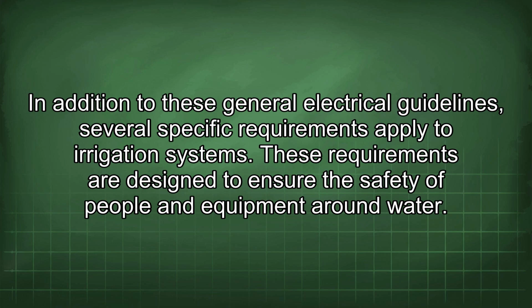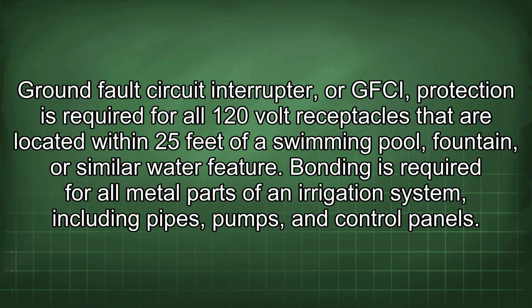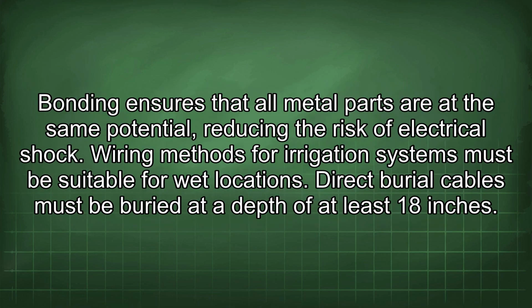These requirements are designed to ensure the safety of people and equipment around water. Ground fault circuit interrupter, or GFCI, protection is required for all 120-volt receptacles that are located within 25 feet of a swimming pool, fountain, or similar water feature. Bonding is required for all metal parts of an irrigation system, including pipes, pumps, and control panels. Bonding ensures that all metal parts are at the same potential, reducing the risk of electrical shock.